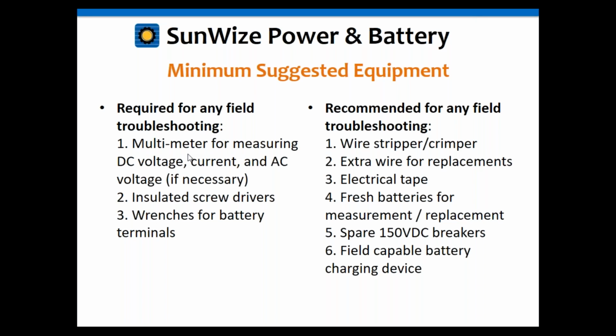Fresh batteries or a portable battery charger can also come in handy if your battery is already at a low state of charge. So being able to swap out the batteries to help with troubleshooting, or being able to recharge those on site, may also be handy. And then sometimes having some additional circuit breakers, DC rated ones, preferably 150 volts, can be handy for troubleshooting.